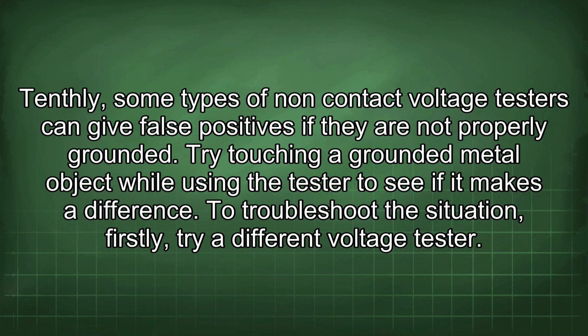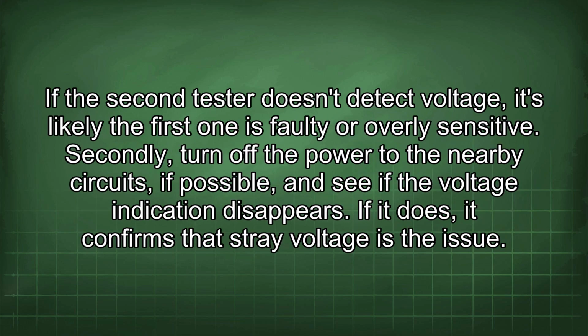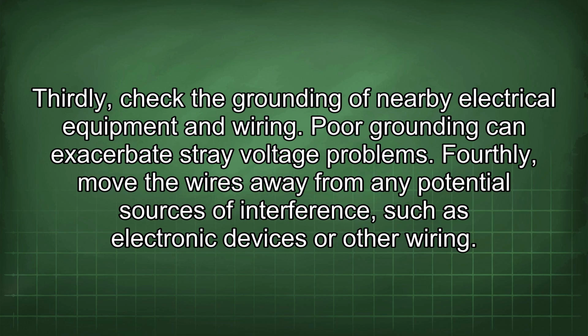To troubleshoot the situation, firstly try a different voltage tester. If the second tester doesn't detect voltage, it's likely the first one is faulty or overly sensitive. Secondly, turn off the power to the nearby circuits, if possible, and see if the voltage indication disappears. If it does, it confirms that stray voltage is the issue. Thirdly, check the grounding of nearby electrical equipment and wiring. Poor grounding can exacerbate stray voltage problems. Fourthly, move the wires away from any potential sources of interference, such as electronic devices or other wiring.